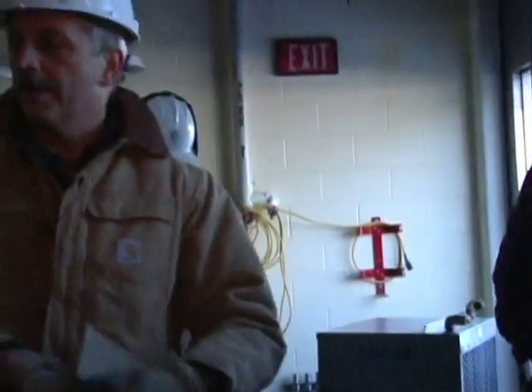Okay, as far as the operation of the bar screen, there's a hand-off-auto switch located directly at the screen itself. If you're running the equipment locally in the hand position, placing this to hand will bring the screen online. If you go to automatic, then that will transfer control of the screen to the panel, which is in the next room. We'll take a look at that as we walk through.